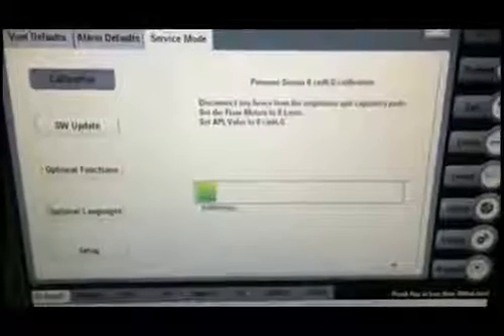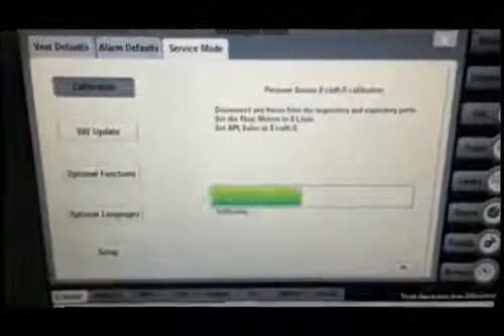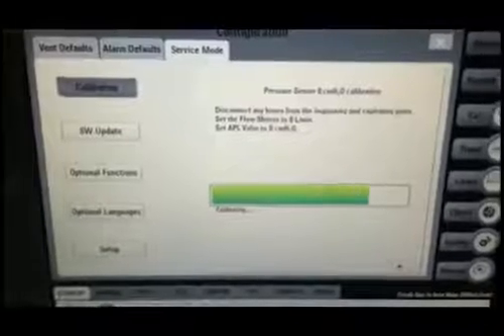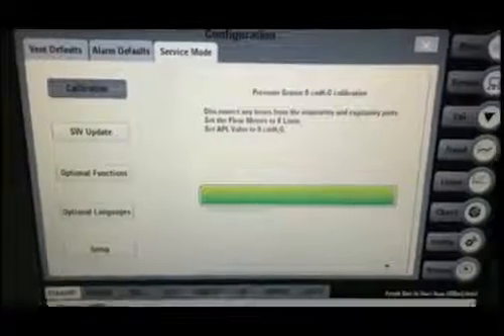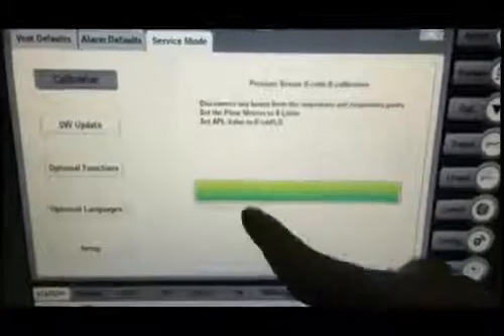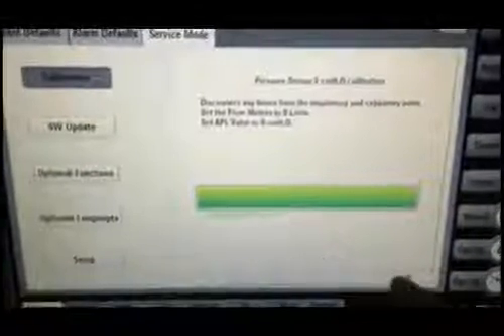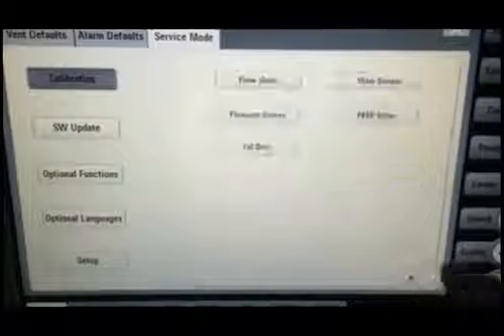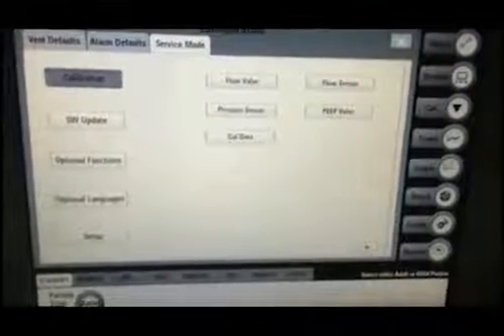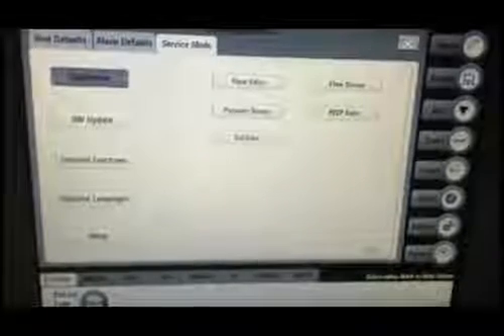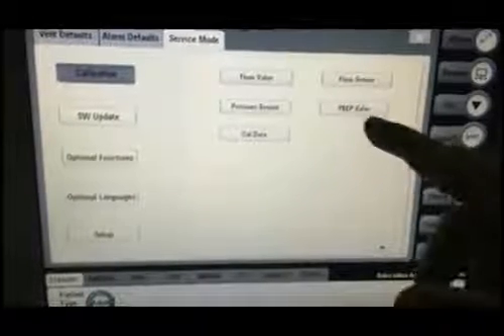After you have performed these 3 steps, please press the start button. The calibration will be performed. After the calibration successful symbol is displayed on the screen, please press the return button. We will perform the PEEP valve calibration. In order to perform the PEEP valve calibration, please press the PEEP valve button displayed in the calibration menu.